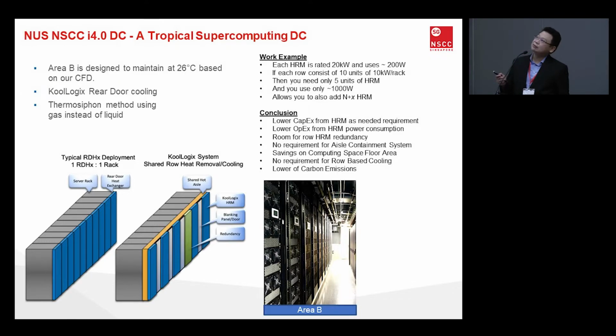It uses a thermal siphoning method using gas instead of liquid. Using gas has its advantage, because that means within the whole area B, there's no water. You eliminate the risk of water ingress. As we all know, computer systems hate water. The moment it touches water, we have more problems. So hence this was used. Most of the rear doors that you see are designed this way.